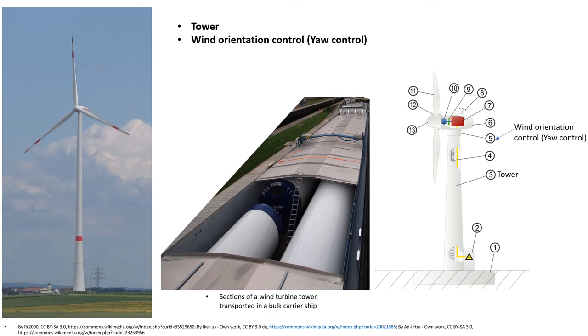Next we shall discuss about wind orientation control, or yaw control. Modern large wind turbines are typically actively controlled to face the wind direction, measured by a wind vane situated at the back of the nacelle, as shown in the picture. By minimizing the yaw angle — the misalignment between the wind and turbine pointing direction — the power output is maximized and non-symmetrical loads are minimized. However, since the wind direction varies quickly, the turbine will not strictly follow the direction and will have a small yaw angle on average.